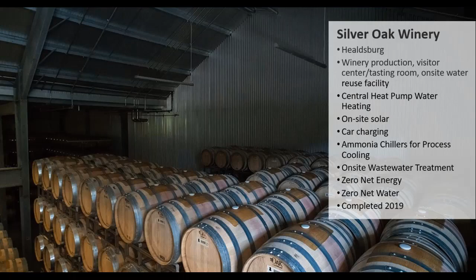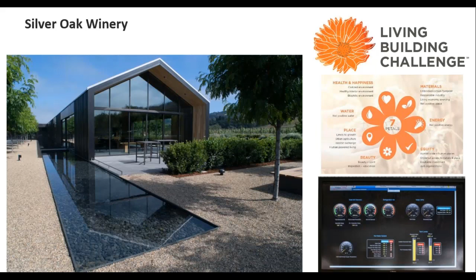This was a living building challenge building, so they weren't allowed to put gas on this project. They're only allowed a small propane backup because they needed additional load for the industrial process wash down facilities. They do a lot of tank washing, barrel washing, winery waste, and have an MBR wastewater treatment, black water treatment system on site. This is an incredible load, almost 16% of the entire winery process. Christine Condon put this project together and was incredibly accurate predicting all these energy use processes, because the developer had to provide on-site power for every kilowatt hour used. So it's a very accurate calculation.